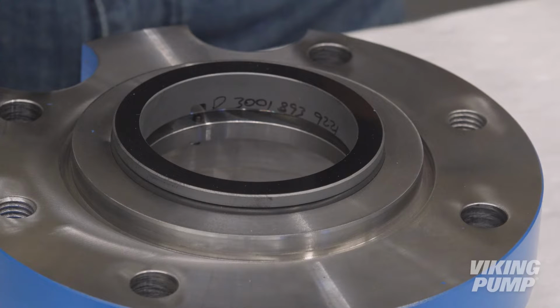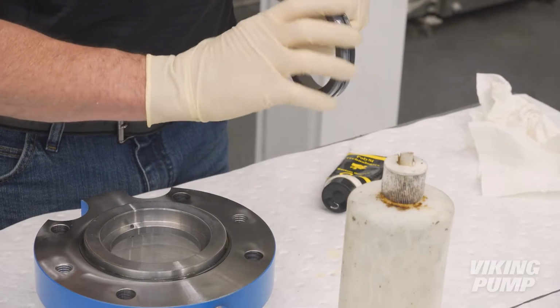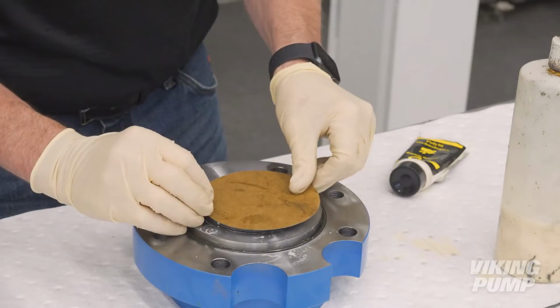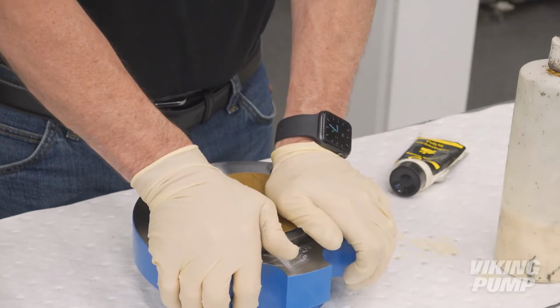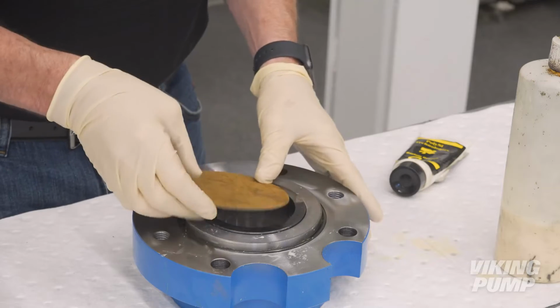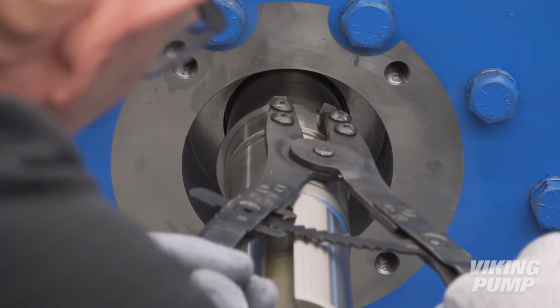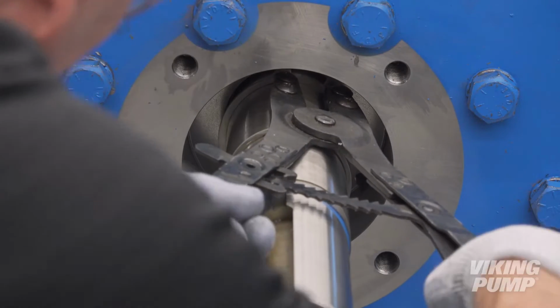Remember that the face of the stationary seat has been lapped to a mirror finish. Any damage will affect the sealing ability of the mechanical seal. Coat with P80 lubricant and install. Install the external snap ring. Make sure it is fully seated.